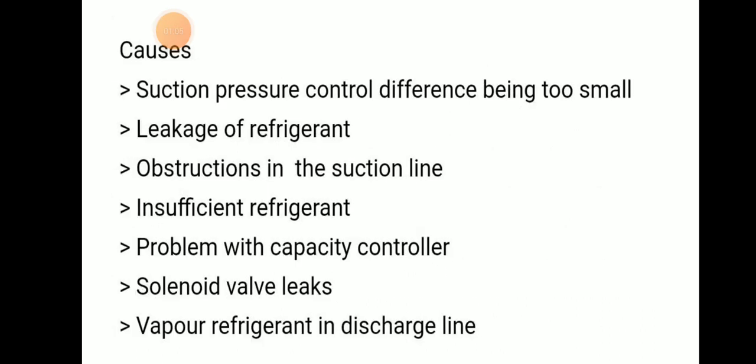The causes of short cycling are: suction pressure control difference being too small, leakage of refrigerant, obstruction in the suction line, insufficient refrigerant, problem with capacity control, solenoid valve leaks, and vapour refrigerant in the discharge line.